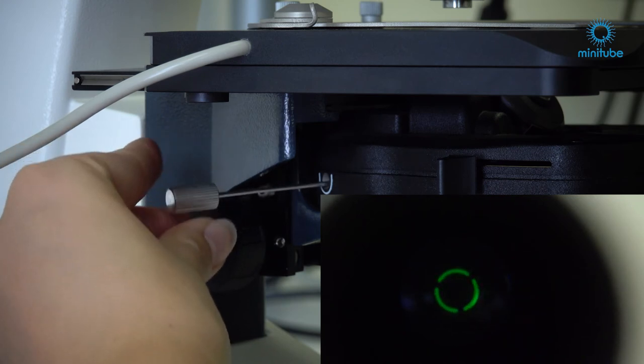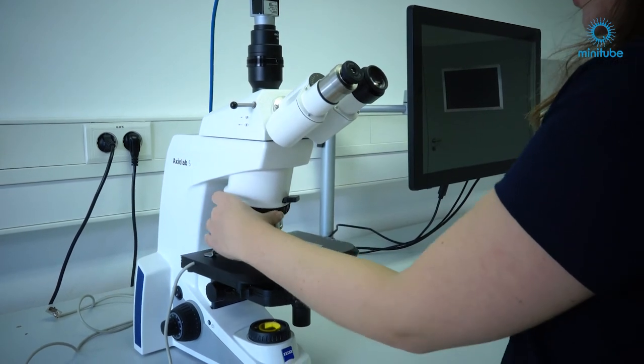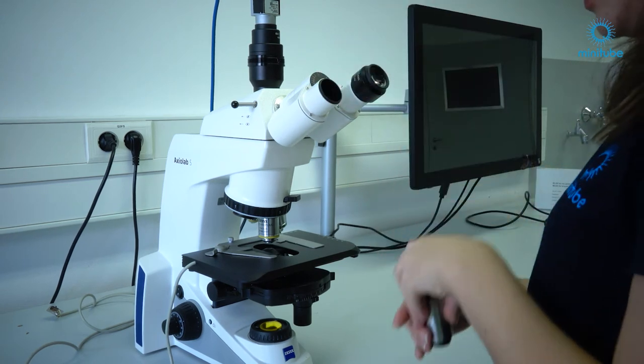When done, repeat this procedure with all the other phase contrast objectives and then replace the auxiliary microscope with the regular eyepiece.